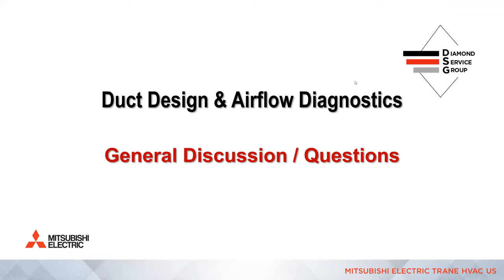Chris, there's a follow-on question about our code, which I don't think you would really be able to address, but I'm hoping you can address the question of putting metal ducts in the attic under cellulose. Yeah. If you do that, you've got to be careful here. If it's an air conditioner and you're going to bury the duct system in cellulose, it needs to be well sealed, and the ductwork should be insulated to begin with in contact with it. What ends up happening a lot of times is people just blow cellulose over it. And if you have any sort of air gap, that's where condensation starts to form. So in air conditioning, yes; in heating, it's probably not going to be a problem.